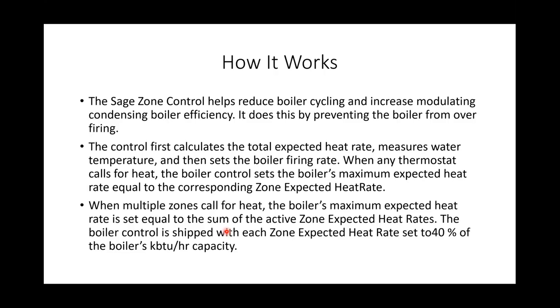You can set each zone up, or you can allow it to kind of quote unquote learn it. There's a zone release feature in there where you leave all the zones set at 40,000 BTUs, it'll release and allow the boiler to modulate to its full range, and it'll figure out where it needs to be over a period of time. That zone release feature is also kind of a backup where if we misjudge it, if we forget to count a room that's connected to the zone, if that zone is not satisfying or doesn't show any signs of satisfying, it'll release the BTU hold and allow the boiler to fire to its fullest firing rate.